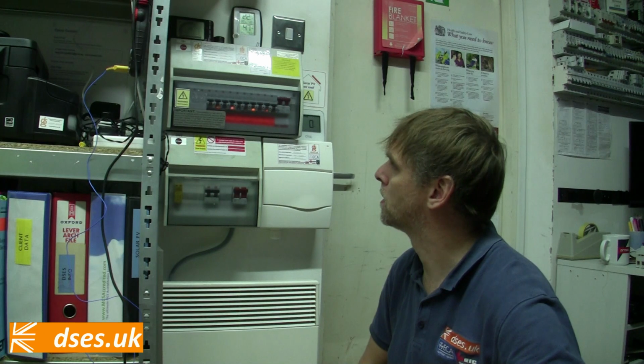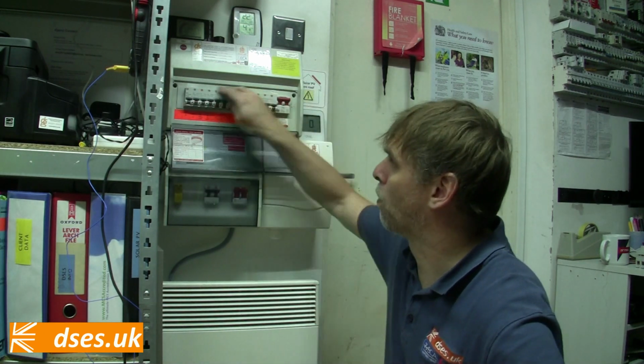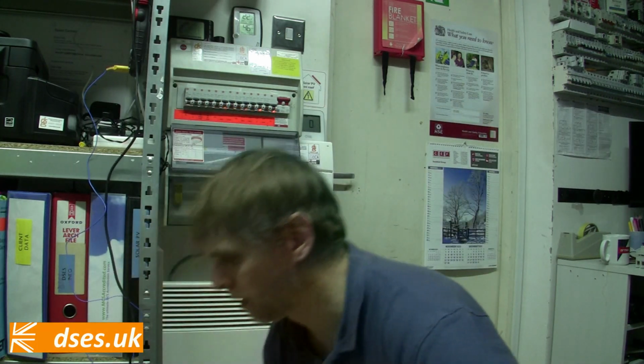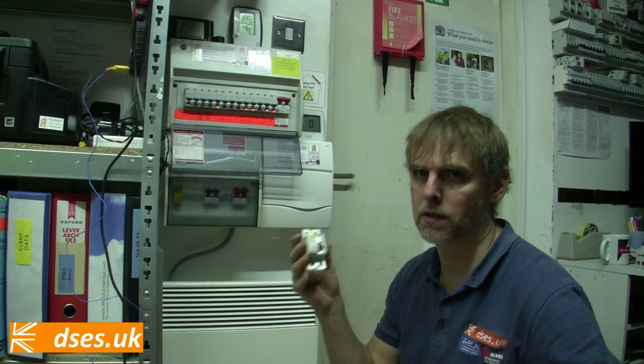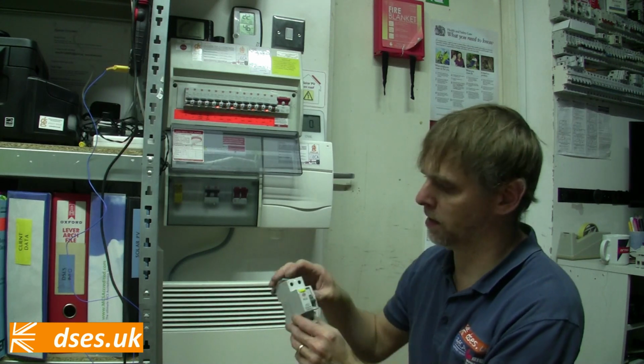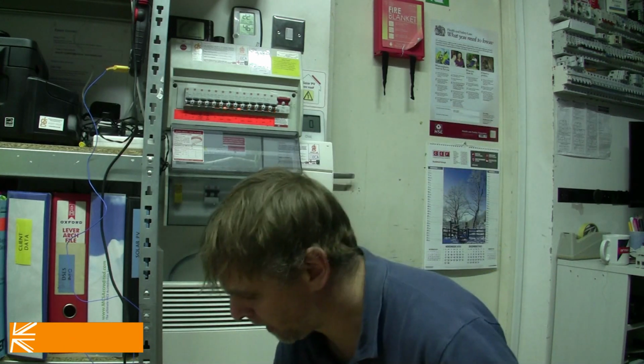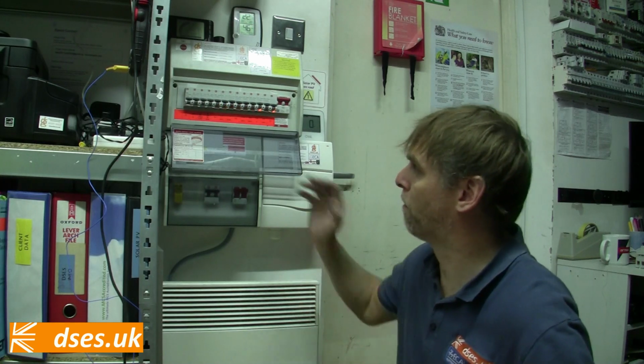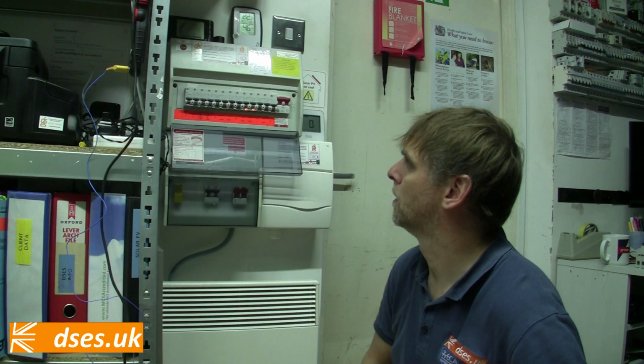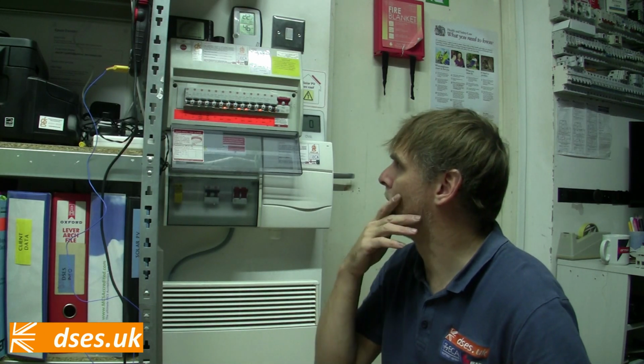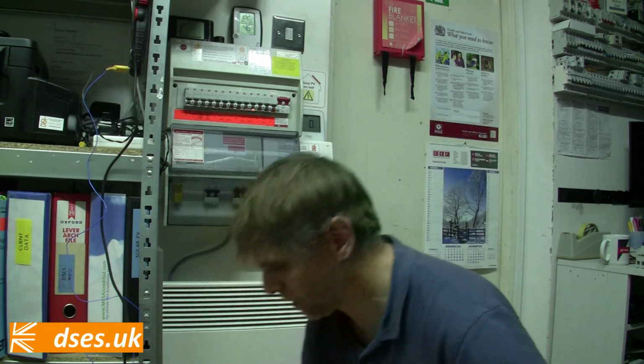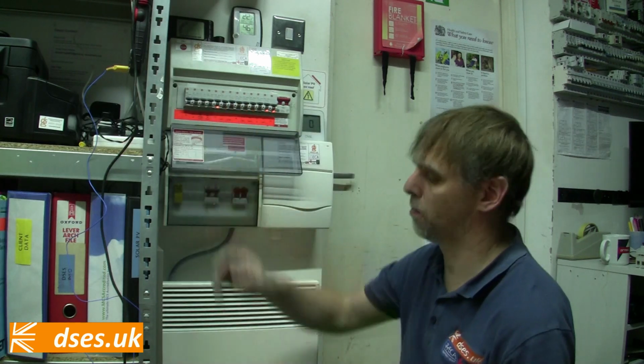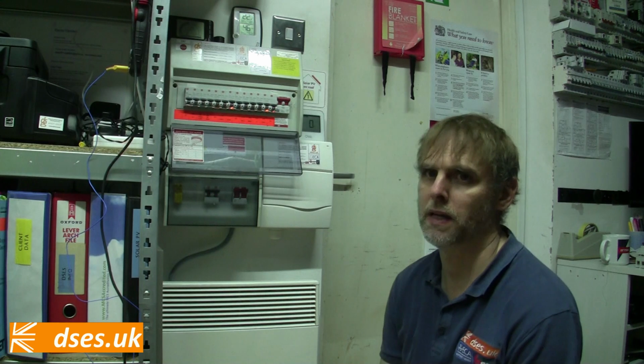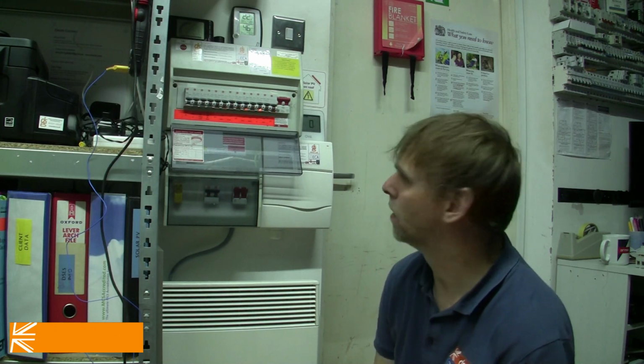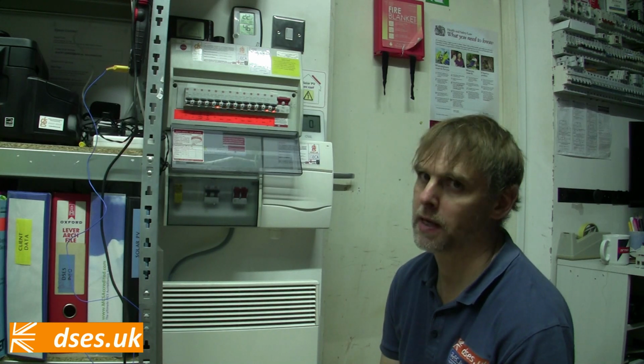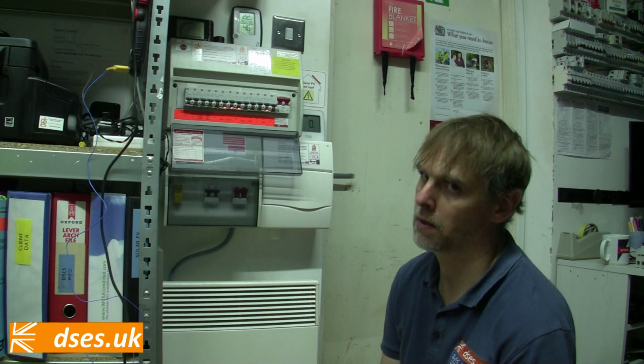One other thing to add, I suppose, obviously these are now all segregated, so there's no common RCD protection like there was before, where one circuit could cause this sort of single point of failure to take out a group of other circuits. Any earth leakage faults now are only going to affect the particular device that circuit is on. And one of the things, well, these are now all Type A devices. Before, the RCDs were Type AC. You can see the AC waveform there. These are now all Type A. So with a certain amount of DC leakage onto any of these circuits, it should still retain its earth fault leakage protection. The mandating of Type As over Type ACs is something you may well see coming in Amendment 2.